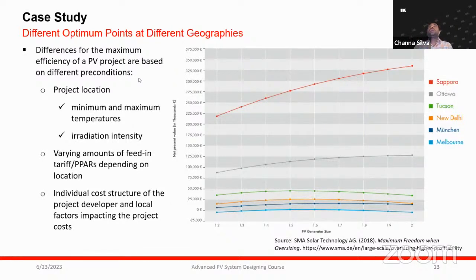Different countries experience winters, low temperatures and low irradiance seasons. For such places, you can oversize more, but first you look at the minimum temperature, where the open circuit voltage shouldn't exceed the maximum voltage of the inverter window. By looking at it, as the location changes, again the oversizing factors can be changed.